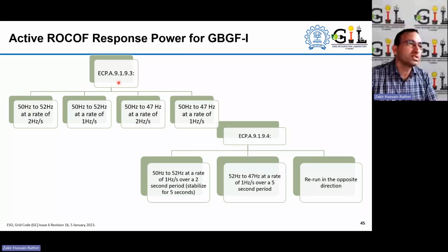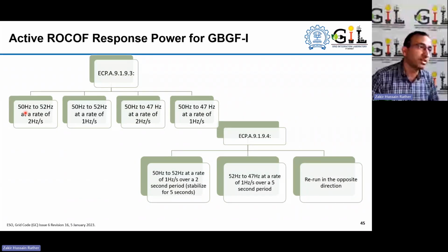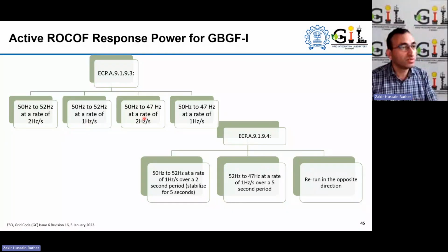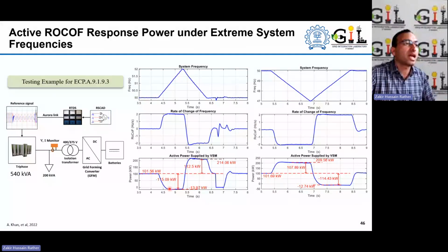For example, in extreme events, there is a 50 to 52 hertz withstand capability at the rate of 2 hertz per second, a 50 to 52 hertz withstand capability at the rate of 1 hertz per second, and a 50 hertz to 47 hertz capability at the rate of 2 hertz per second. And this is the full range requirement. For example, here you can say 50 to 52 hertz at the rate of 1 hertz per second over a 2-second period, and then it will stabilize for 5 seconds. So there are these additional capabilities that could be required by the grid code regulations for grid forming technology.